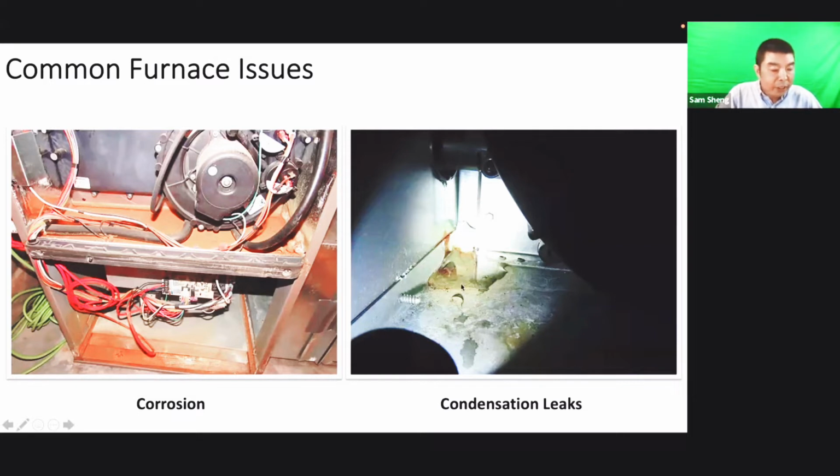So this one is a leak from the furnace. But sometimes for the category 1, if you see the rust there and there's no air conditioner, maybe there's a humidifier. Humidifier causes the same trouble as the A coil. If they didn't have maintenance, the water just drips from the inside of the furnace and causes the same trouble. So this one looks like not a leak from the furnace, but like the humidifier or possibly the A coil.